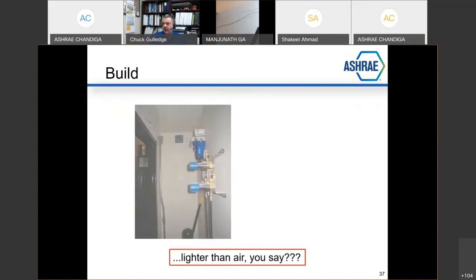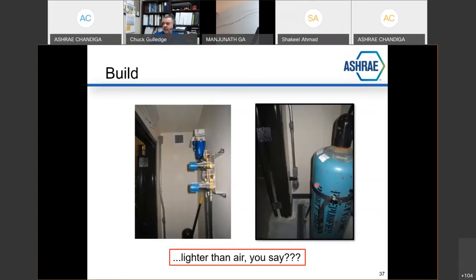Lighter than air, you say. Okay, you can see the top of a bottle tank here, and we got some action going on, and this gas happened to be lighter than air, so the exhaust got put in the correct spot for that room. But look at this conduit. Where does this conduit go? I wonder where it goes. Oh, it goes to the gas sniffer that's associated with this level of gas that once it leaks, it collects high in the room. Well, they had to rewire this and move the gas sensor up to where the danger detection zone was for the gas in question.